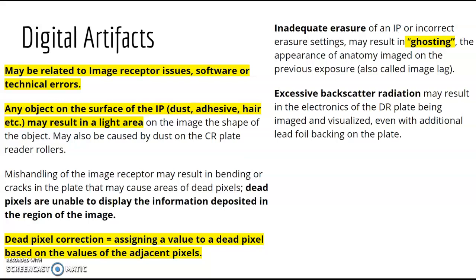Mishandling of the image receptor can result in bending or cracks, and may cause areas of dead pixels. Dead pixels can't display information, so you might see a small white area that keeps coming up. In room 5, there's a dead pixel — I see it most often on lateral chest x-rays. There's a term called dead pixel correction: it assigns a value to a dead pixel based on the surrounding pixels and collects them together.